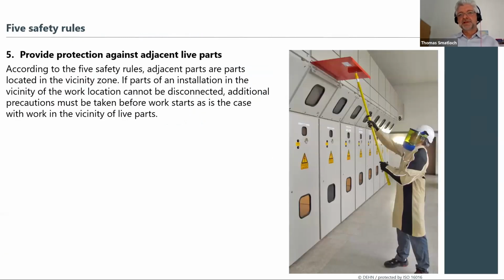Good. So let's come back to our safety rules. Rule number 5 is about the insulation of adjacent parts of the installation which still have voltage, and to make sure that parts of that cannot be touched unintentionally, there should be an extra insulation, as we can see here. In this case, we have a special switchgear cabinet where the opportunity for such a shutter is relatively high. So that's why there is a tool for this as well, to fit this shutter in the installation.